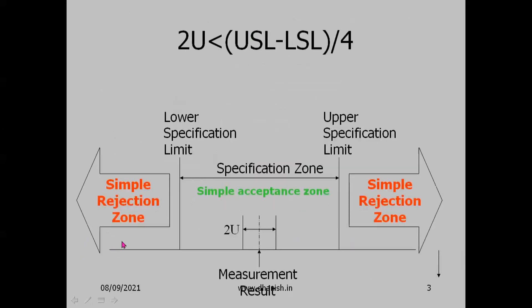Graphically, the upper specification limit and lower specification limit define the specification zone, which is the acceptance zone. Beyond this is the rejection zone. The measurement result is plotted, and then plus or minus 2U (capital U, the expanded uncertainty) gives the coverage interval.